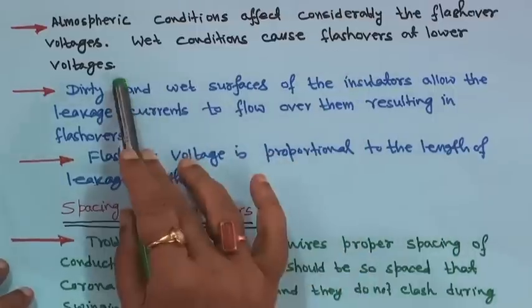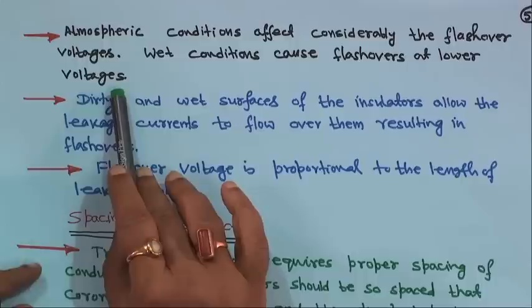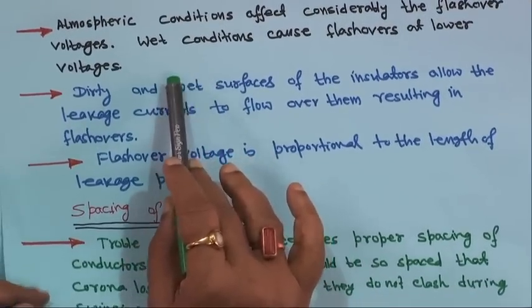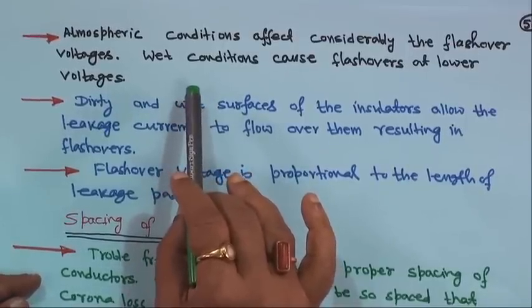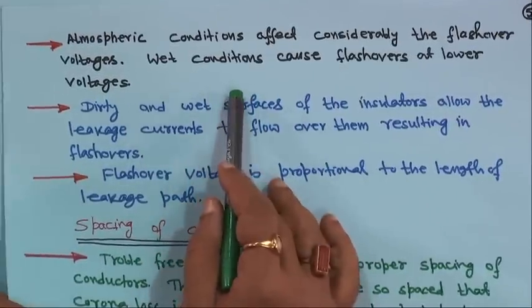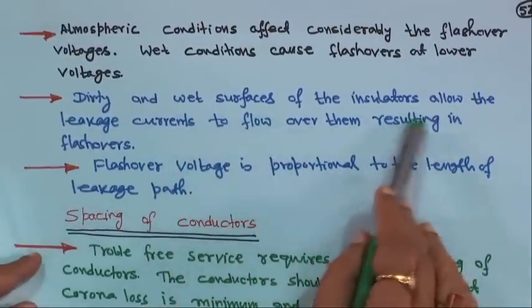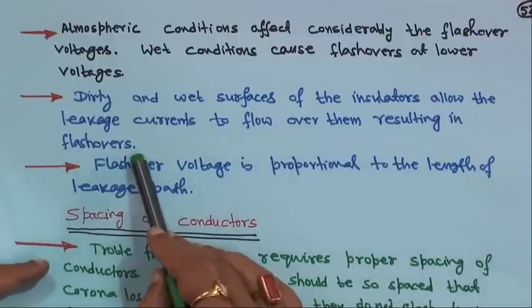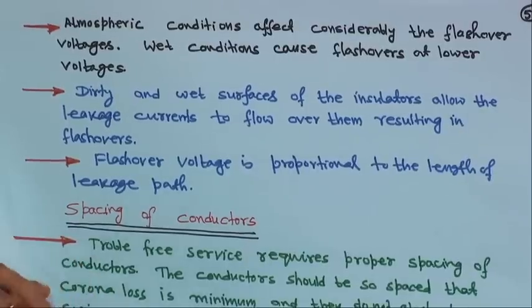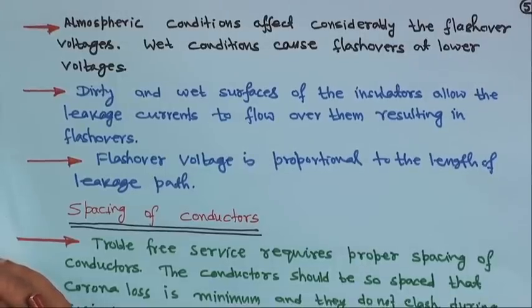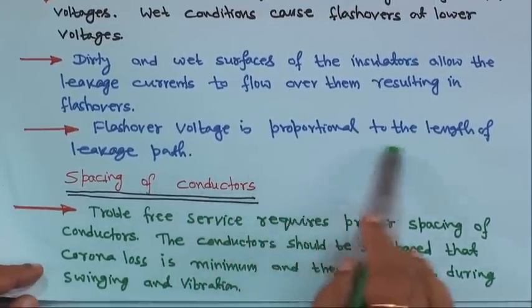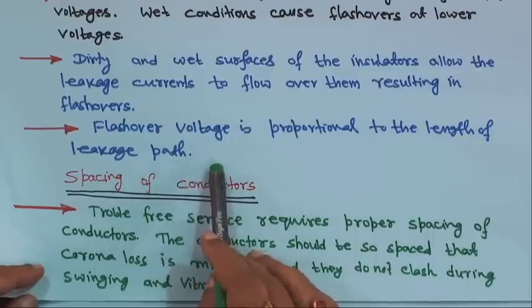Wet conditions cause flashover at lower voltages, particularly during rainy season — this can create problems. I have observed flashover happening during rainy season even in railway traction lines. Dirty and wet surfaces of the insulator allow leakage currents to flow over them, resulting in flashover. However, it does not generally spoil the insulator — the insulator can withstand such flashover. Flashover voltage is proportional to the length of the leakage path.